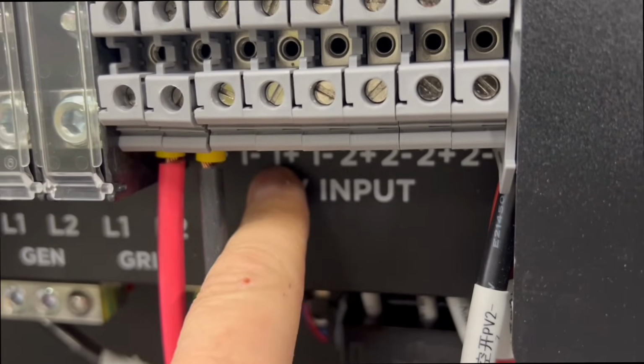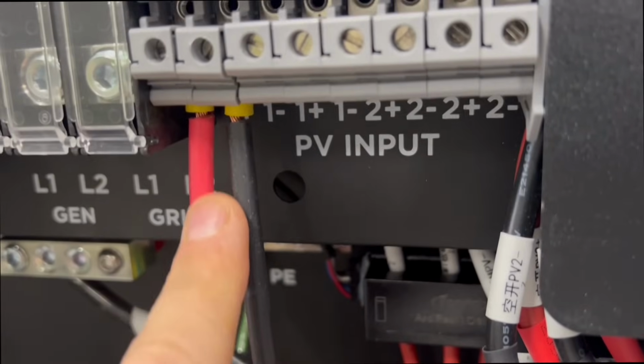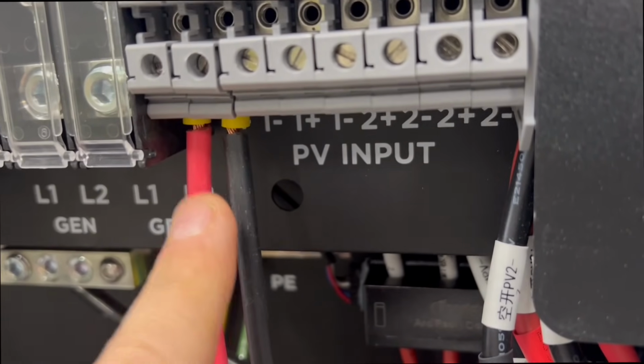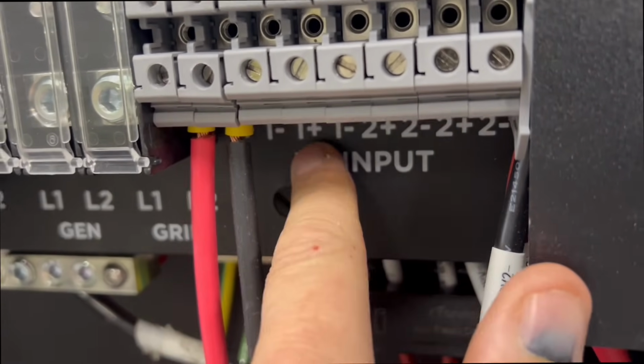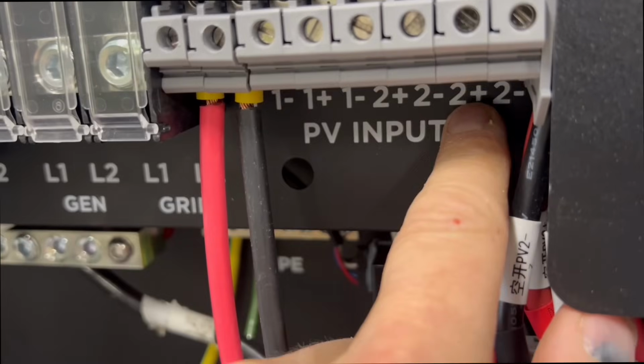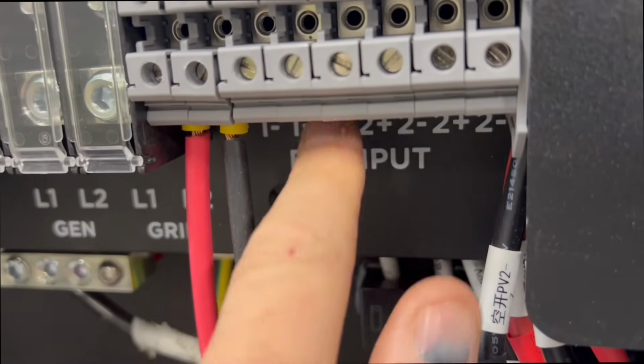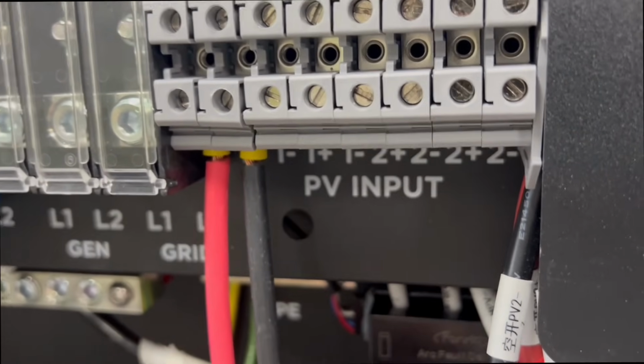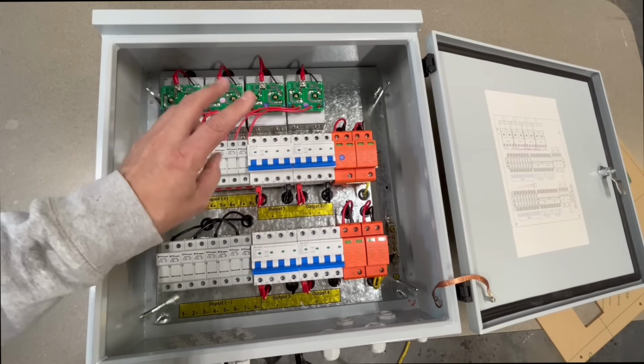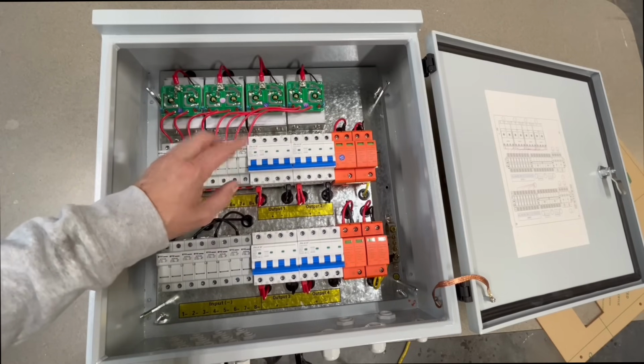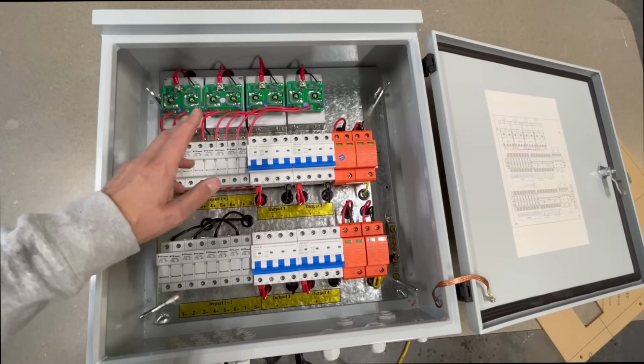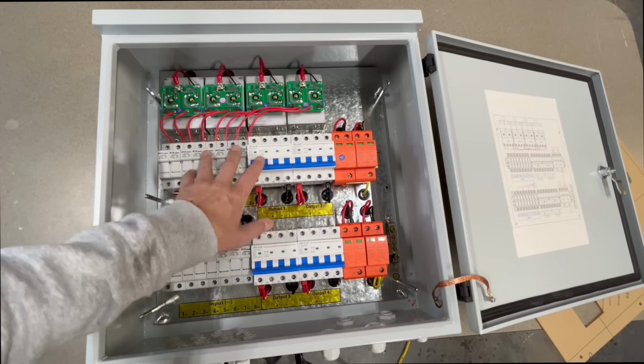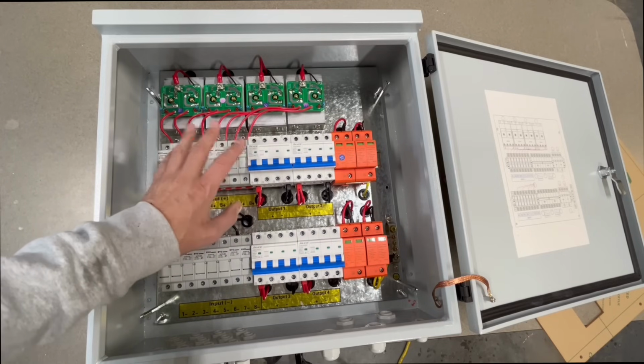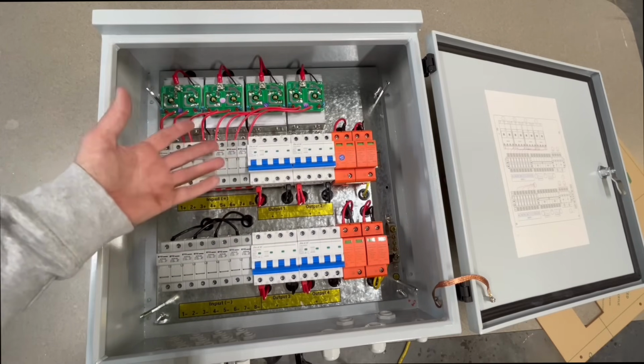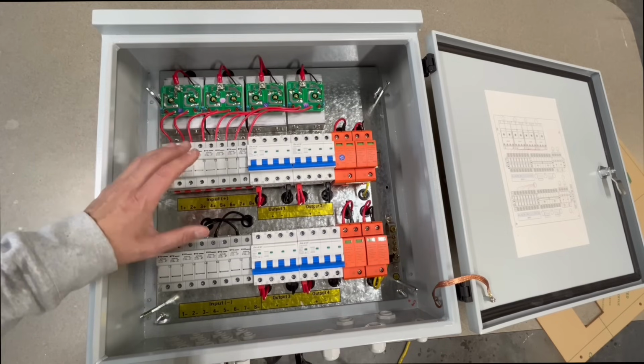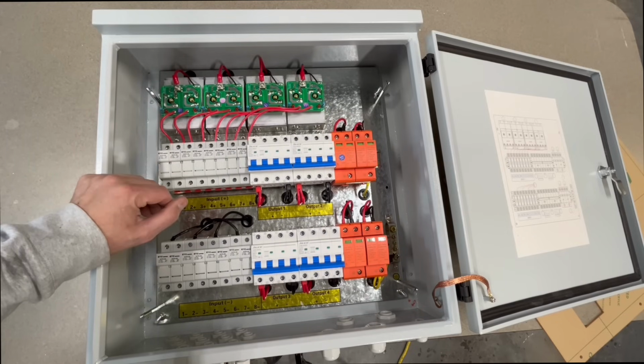And then this is going to be the second string. So you'd have two strings that are actually combined before they get here. So that's two and one. And then we have a third right here. And you would do the same with input two. So you've got one, two, and three to equal that 12,000 watts. But you only have two different inputs on input one and two different inputs on input two. So you can put two strings into the 12,000 XP without an issue, but you really wanted to put three in it. How to accomplish that in the easiest and safest way is really the question or the goal.